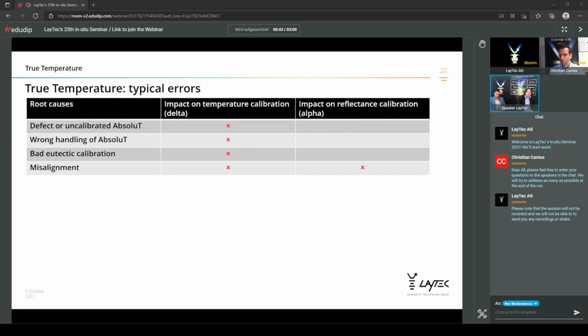Misalignment is a very essential and really important item. Misalignment refers to the general optomechanical alignment of the entire setup of the Epicurve TT or the Epi-TT, or even of the Pyro 400 or P400 unit. You might all know that the Epi-TT as well as the Epicurve TT, consisting of the Epicurve laser head with the Epi-TT head attached to it, are mounted on top of the reactor, on top of the viewport, with a mounting unit. And this mounting unit allows a fine positioning adjustment or alignment adjustment in both a linear Cartesian X and Y orientation, as well as an angular tilt adjustment in both directions, in a radial adjustment as well as in a tangential angular adjustment.